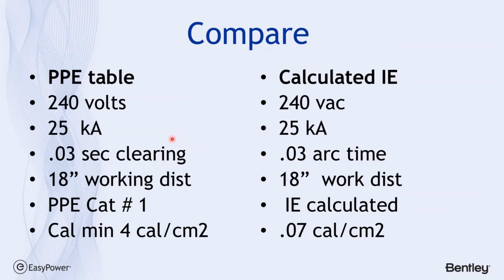This was an exercise I ran through, and this is not cast in stone. It's just a little exercise where I used the conditions in the PPE table to determine how they calculated incident energy. If I did a category 1 comparison, it came up with 4 calories as the rating that I should have on my PPE. If I went in and just calculated the incident energy based upon the same parameters, the model allows me to have less than 1 calorie per square centimeter PPE. So what I see is there's a fair amount of guard banding in the lookup table, which you would expect, and that's why just crossing the boundary there is a dicey operation.